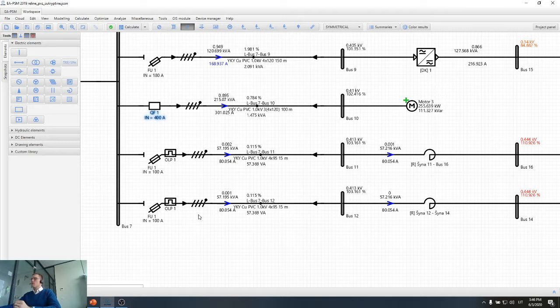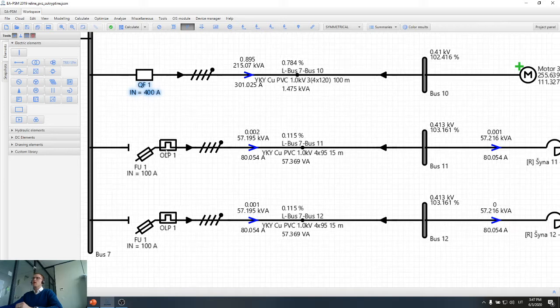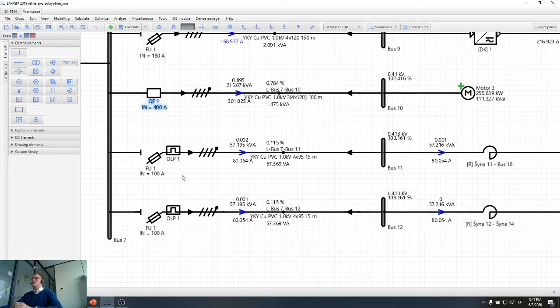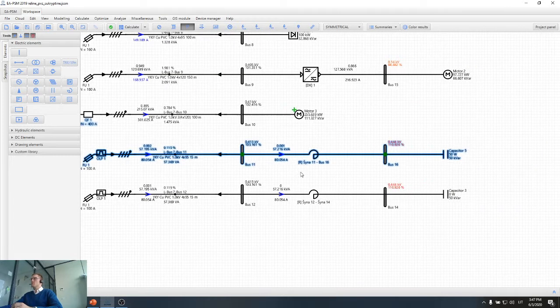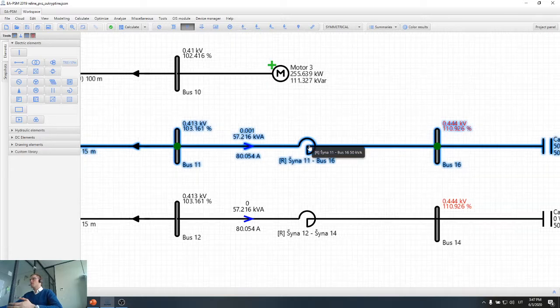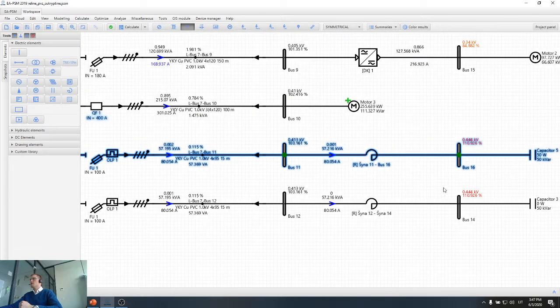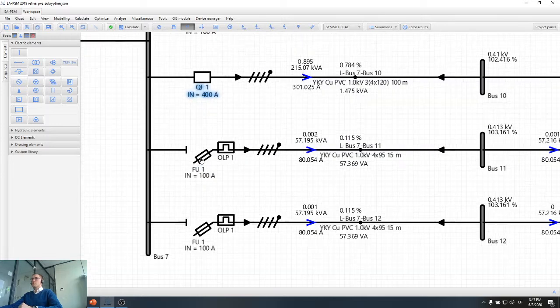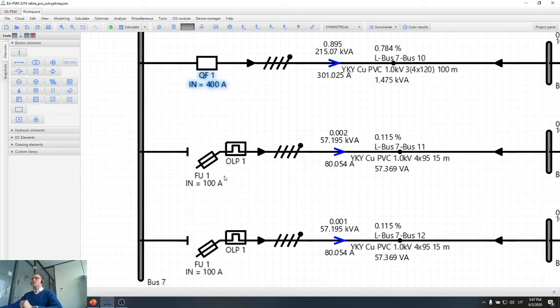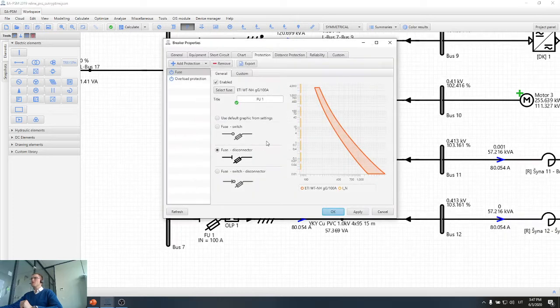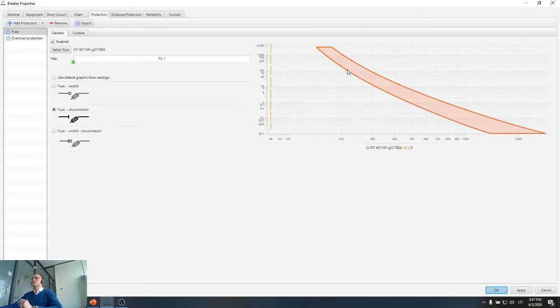What is more, we need to have a backup protection for our automation device. So it is also recommended to use an overload protection device. Here, this is a thermal relay, which in case of overload will disconnect the whole system here, the harmonic filter and the fuse and the capacitor itself. So we have even two protection devices connected. Let's open the system and see how to set two protection devices.